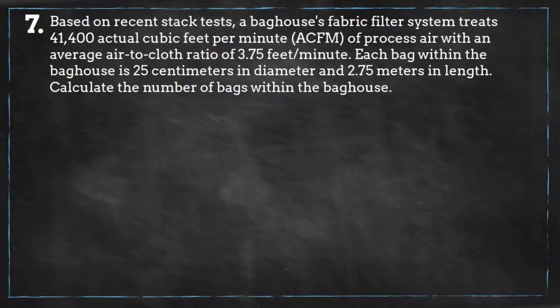Based on recent stack tests, a bag house's fabric filter system treats 41,400 actual cubic feet per minute of processed air with an average air-to-cloth ratio of 3.75 feet per minute. Each bag within the bag house is 25 centimeters in diameter and 2.75 meters in length. Calculate the number of bags within the bag house.